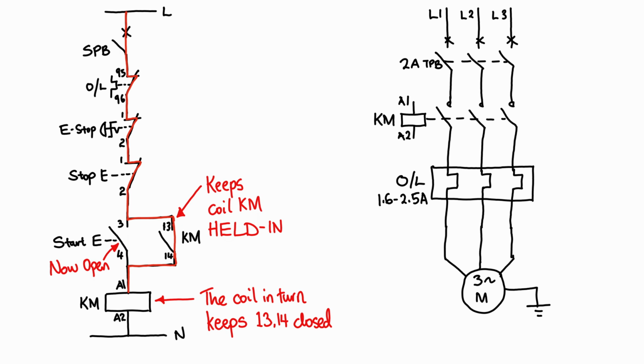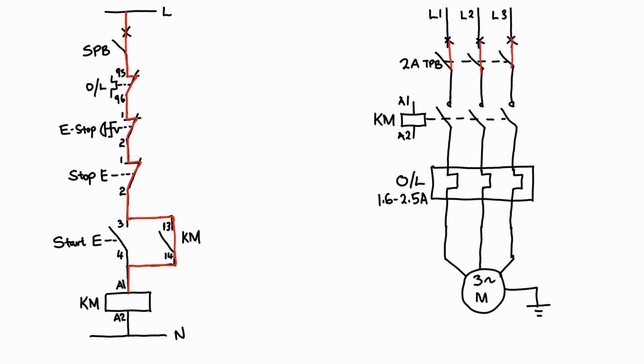It will only stop if it's interrupted, maybe by pressing the stop button in normal operation, or by pressing an e-stop in an emergency situation, or if the motor trips due to an overload. The three-phase circuit breaker will be switched on here, and when this contactor engages, it closes these contacts and current will flow to our motor windings. We'll switch on our supply voltage, current flows to our motor windings, and our motor starts to rotate.